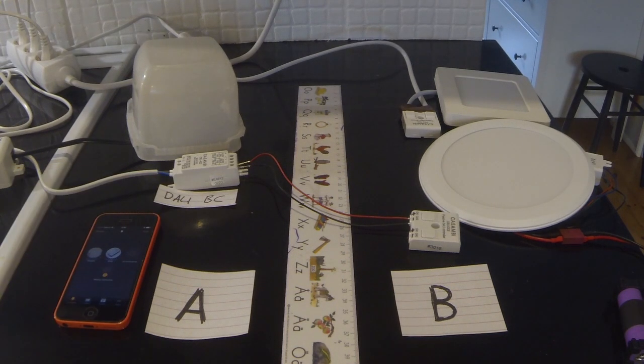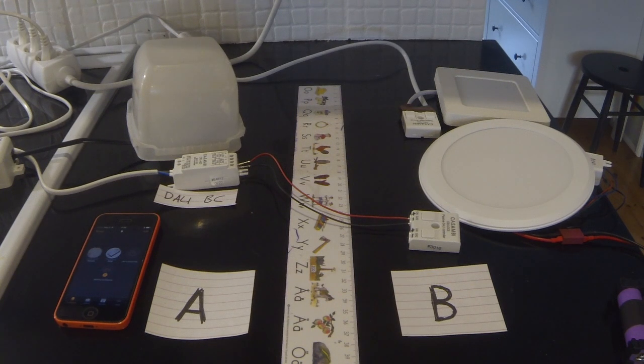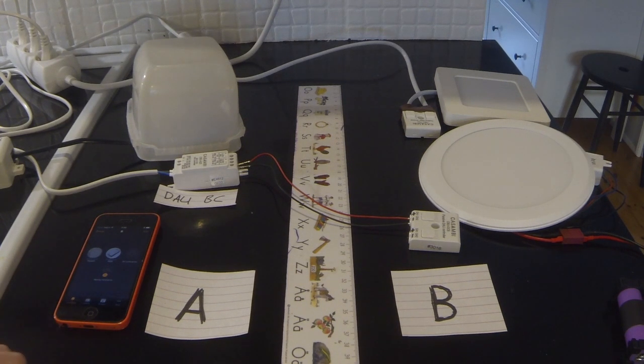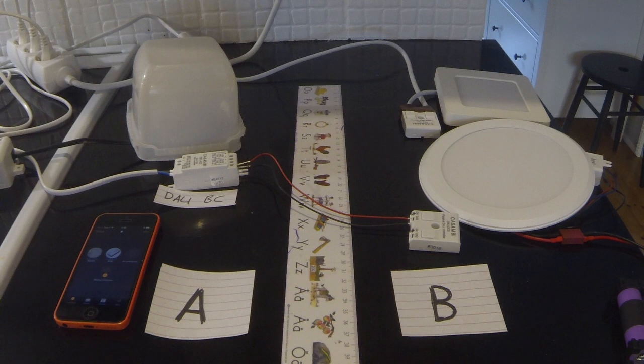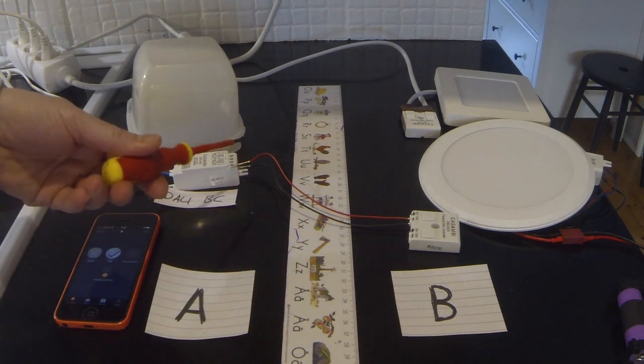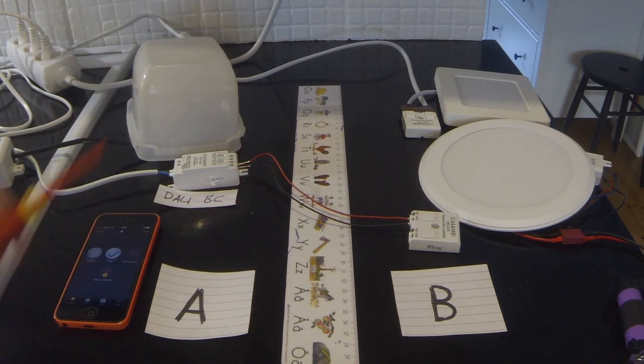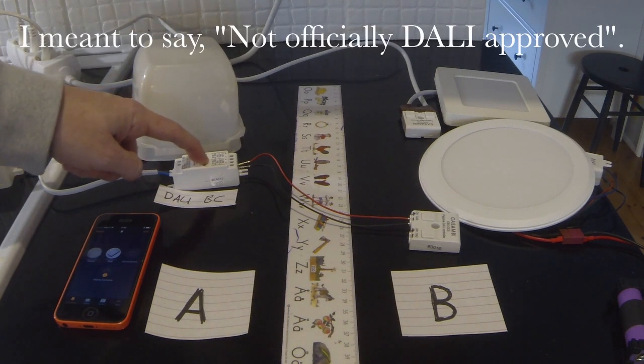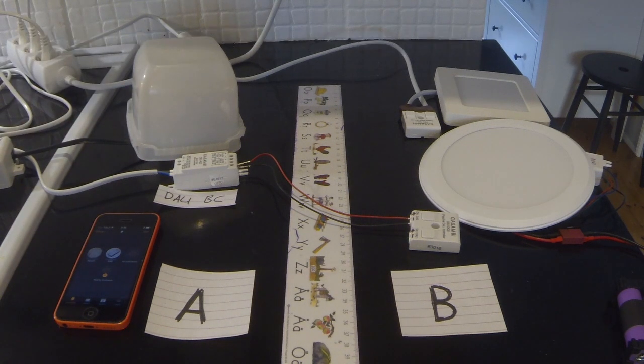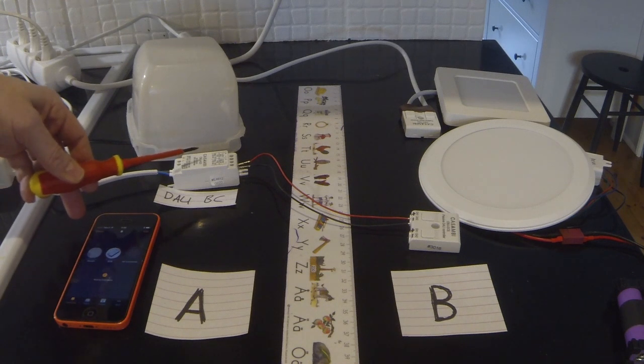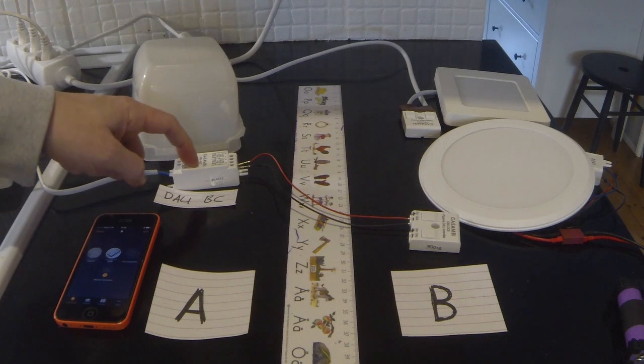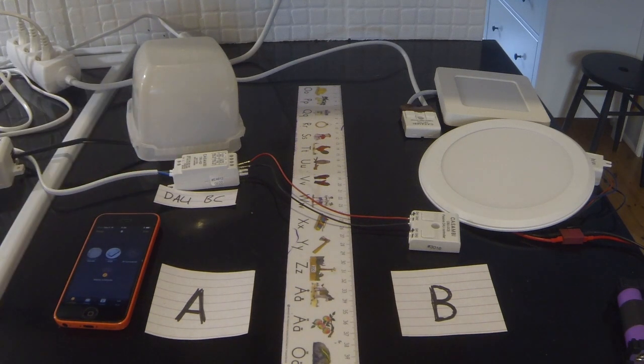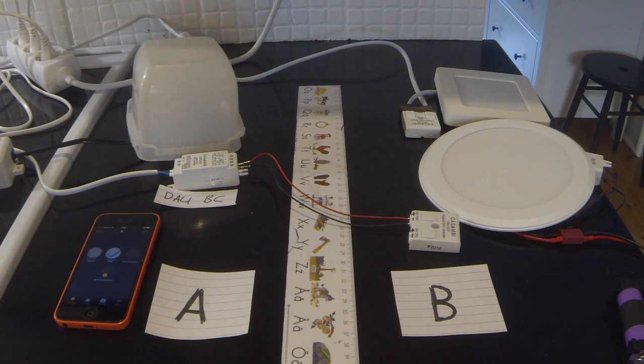So that was it really. It might sound, or it might seem a little bit complicated, so you might want to watch this video once or twice, or a couple of times to get used to it. Theoretically, it could be used for all sorts of reasons, but like I said, the only thing you would need to test through trial and error is how long these wires can be. The true DALI limitation is 300 meters. However, the Casambi devices are not officially DALI approved. They don't have the DALI label on them. Pretty much because they're using a slightly lower voltage than DALI, so you would never get anywhere near the approved 300 meters from this device. I can't offer any advice as to how long that wire could possibly be. Again, you would have to test it through trial and error.